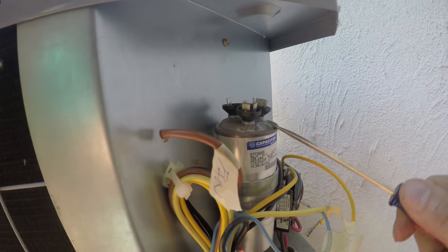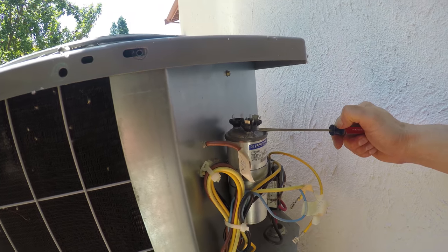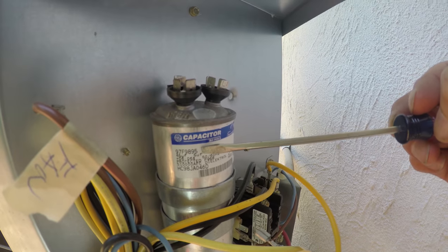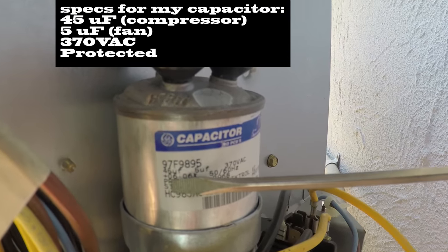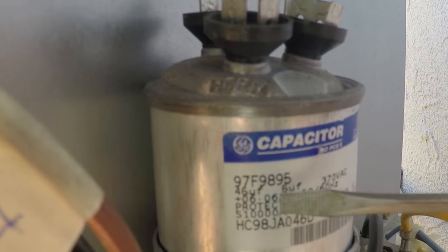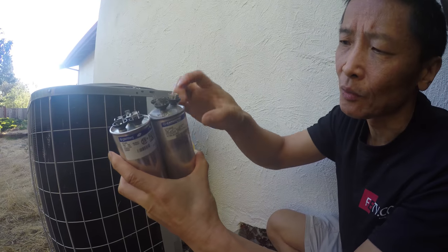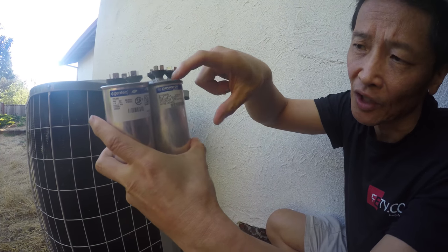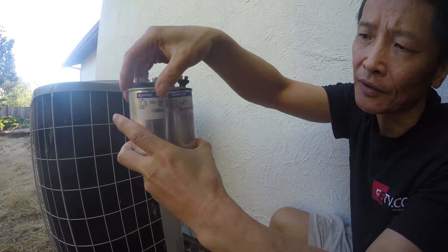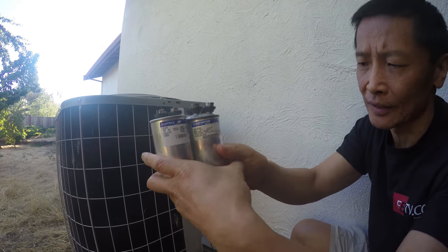See how it's bulged — this is not flat; it's getting higher in the center. There's a liquid inside that heats up and causes it to pop. Here's the replacement capacitor made by GE — the part number shows it's a 45 microfarad for the compressor and 5 microfarad for the fan. The old one is bulged out; the new one is very flat.